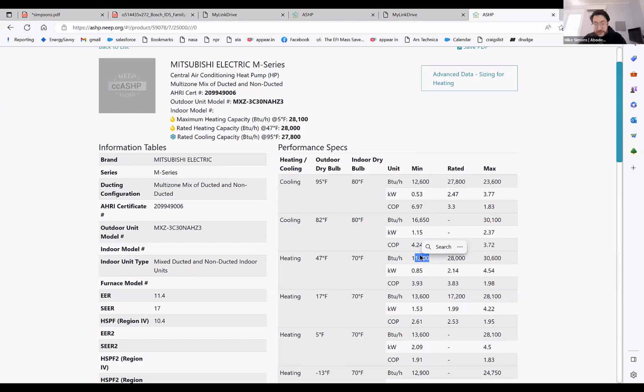Yeah, the min on here looks really good, in my opinion. Why? Because it's supposed to be for heating, right? So you don't want them... I guess I got it totally wrong. So the min, why does it look good if we need 32 and it says 11? I would be looking at the max at 5 to see what its total heating output would be. So we're looking for 32. This is 28.